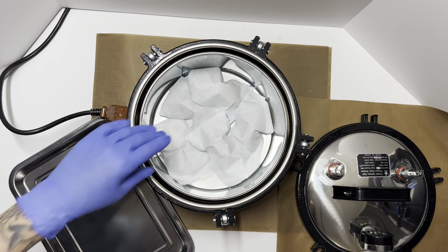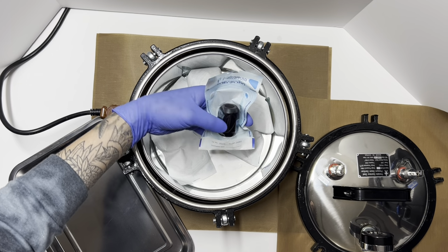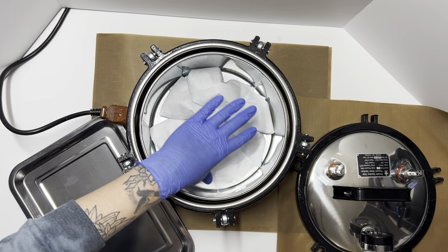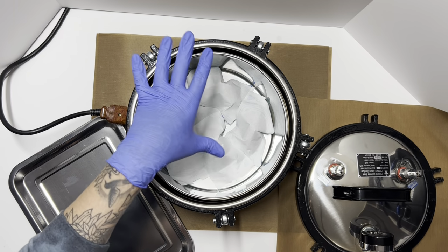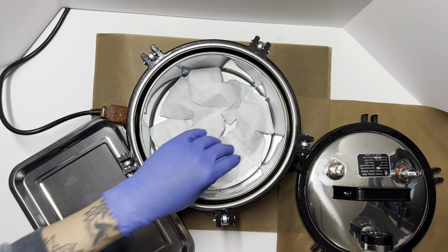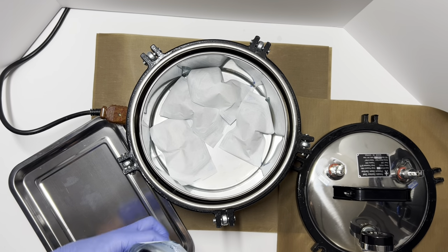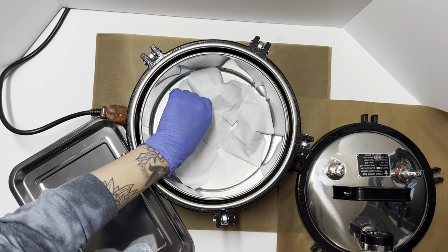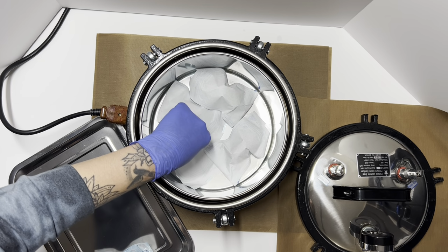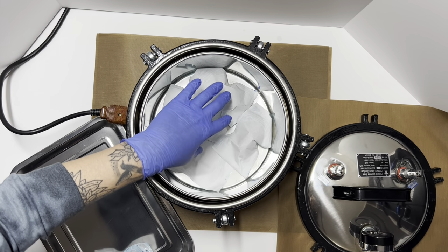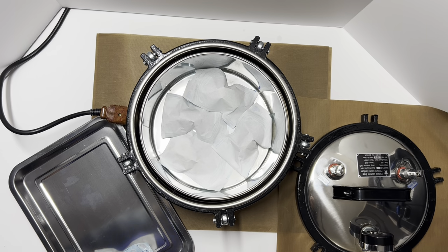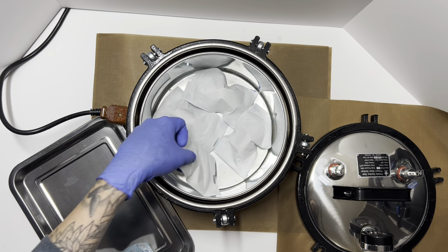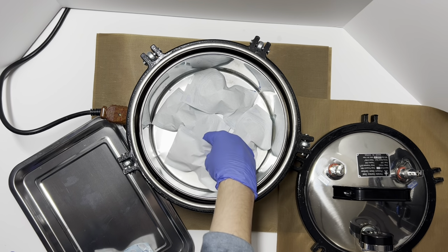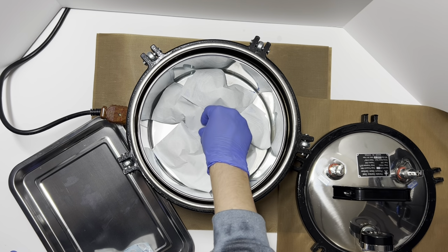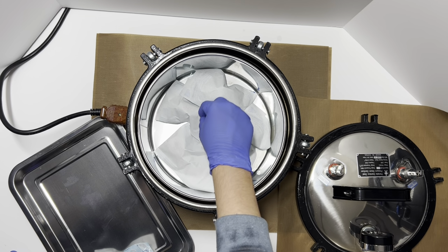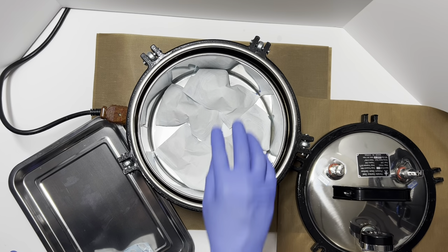So something like this, I'm not sure if this would be fully acceptable if I want that, because I would like the steam to evenly go throughout each and every pouch. So what I can do is I can simply remove one, and then we can get that one on the next batch and kind of know your limits. So for this, comfortably, I want to do four at a time, as you see right here. And just make sure that everything is as best as it can be. You don't want anything overlapping each other or anything like that.